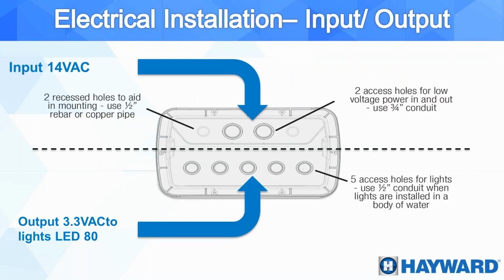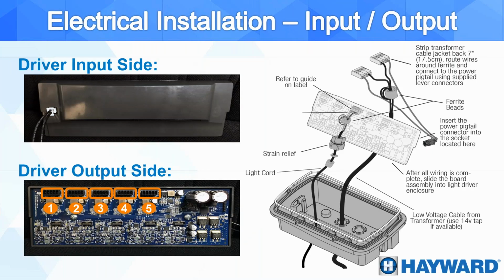Here we see the electrical installation on the ColorLogic 80 driver. On the top is our input. Remember that our input is low voltage, 14 volts. That is going to be feeding our controller. And then we have a couple of access points on the bottom of the controller. This is the bottom of the controller that we see here. And then we're going to output into our ColorLogic 80. We have 1, 2, 3, 4, and 5 outputs, because remember that we can feed up to 5 lights with one of these drivers. Now, how does it look on the inside?